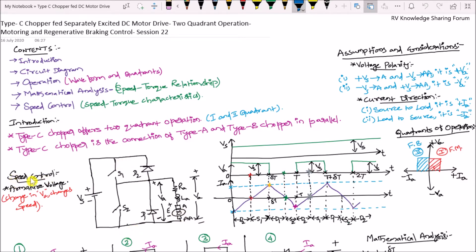Speed control is achieved using the armature voltage control method. When we change the armature voltage VA, we can change the speed. In order to achieve a change in the output voltage of the chopper, we change the duty ratio. When the duty ratio is changed, the output voltage of the chopper changes, the armature voltage changes, and ultimately the speed of the motor is changed.